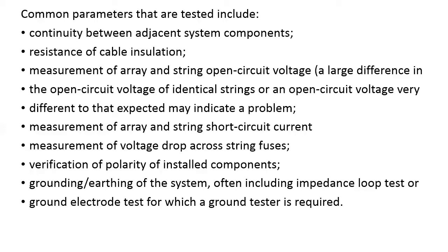Then the measurement of the array and the string open circuit voltage. We have to check the measurement of the array and the string open circuit voltage. If there is a large difference in the open circuit voltage of identical strings, or an open circuit voltage very different to that expected, it may indicate a problem. So you have to ensure that the measurement of the array and string open circuit voltage is checked. Then the measurement of array and string short circuit current has to be checked.